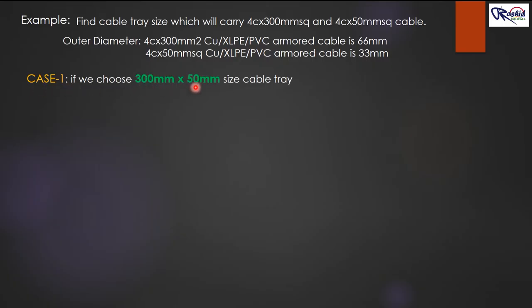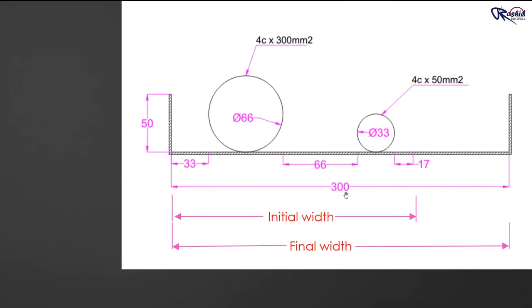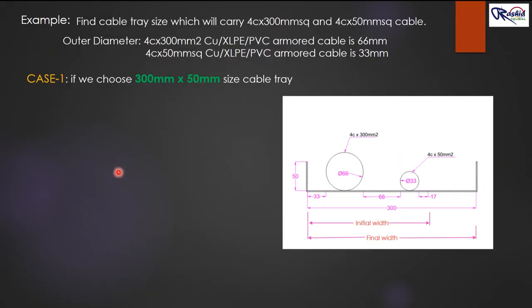If we select a 300 × 50 mm cable tray in case one, the arrangement is: tray width is 300 mm and height is 50 mm. The first cable laid is 4-core 300 mm² and the second is 4-core 50 mm². The gap between these two cables equals the diameter of the bigger cable, which is 66 mm. On the left side we keep 33 mm (half of 66 mm), and on the right side we keep half the diameter of the 50 mm² cable, which is approximately 16.5 mm, rounded to 17 mm.